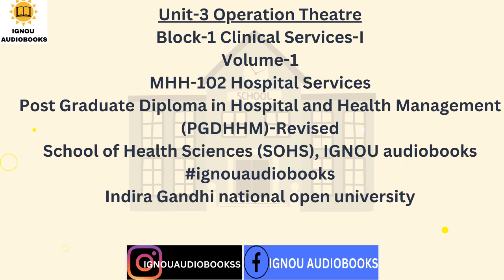Modular OT specifications: absolute flatness, vertical level adjustment of subframe, hermetic sealing, sound insulation, non-flammable materials, ease of disassembly, individuality of panels. Benefits of modular OTs in the hospital: imaging diagnostics during operation, patient safety, collaborative environment, cost savings. There are 4 major components that need to be installed in modular OTs. This includes 1. Control panel, 2. Ceiling mounted laminar flow, 3. X-ray screen, 4. Surgical scrub platforms.